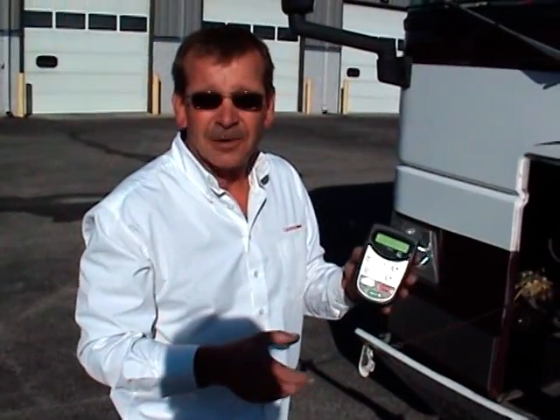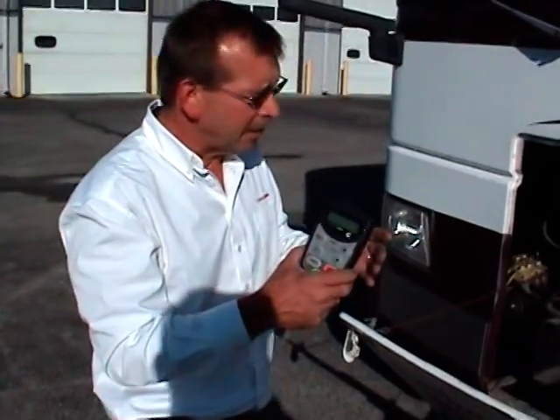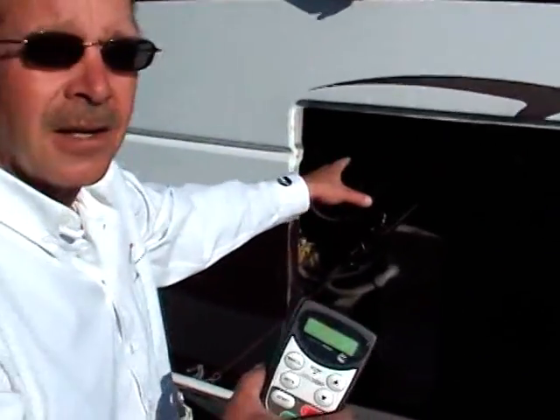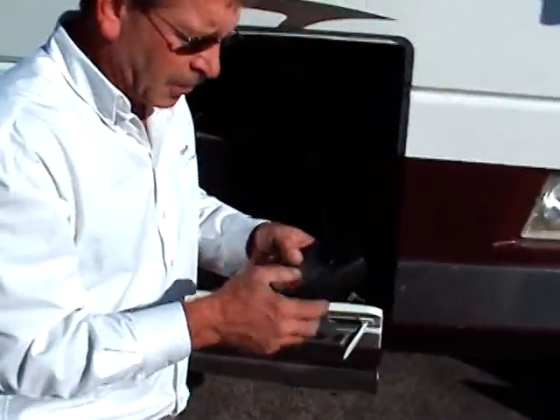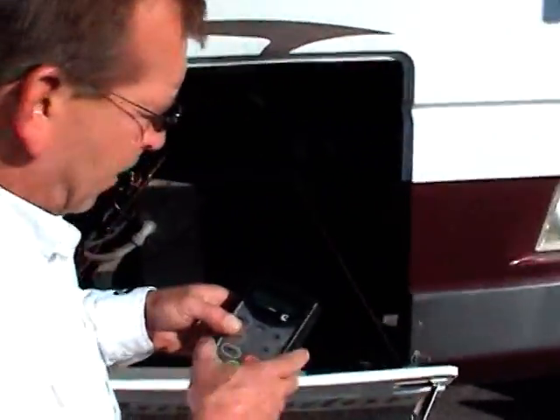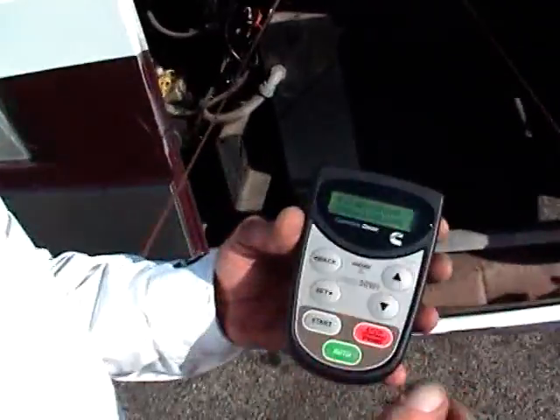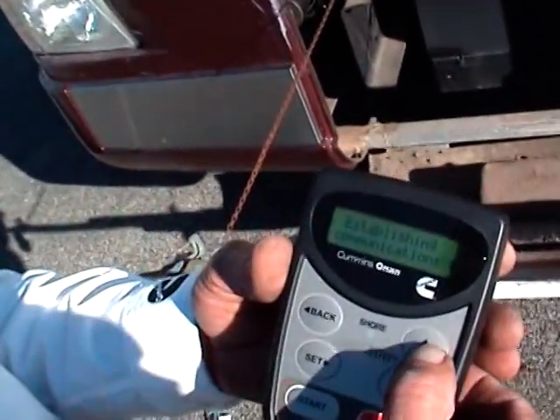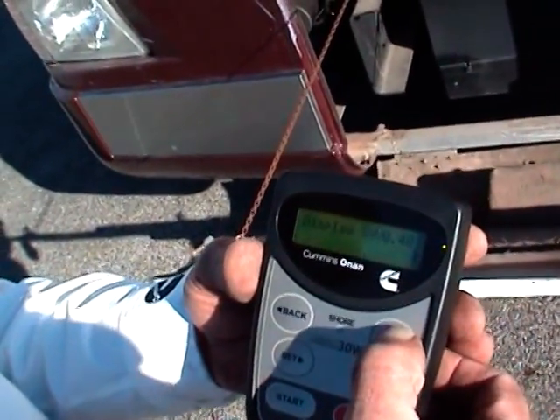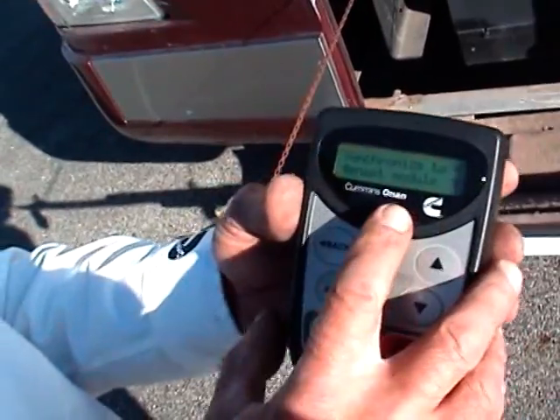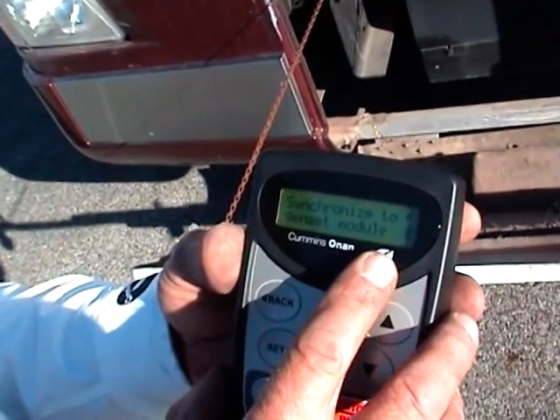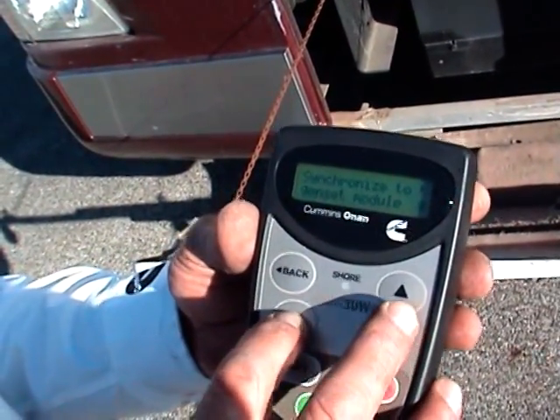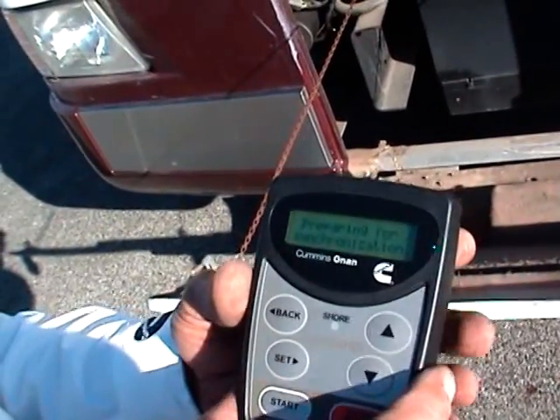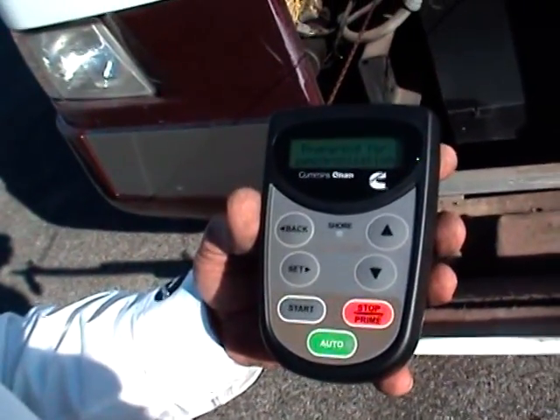Now we're going to synchronize the display module to the genset module we just connected. When you hit any button, it comes up showing establishing communications. Scroll through the screen until you hit the one that says synchronize to genset module, then hit your set button. It's preparing us for synchronization.